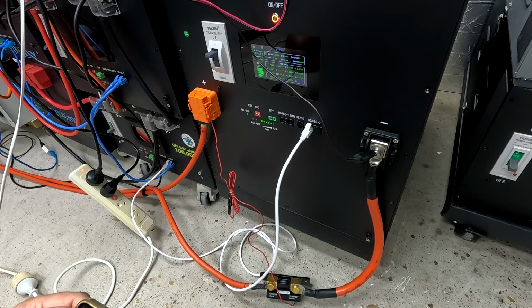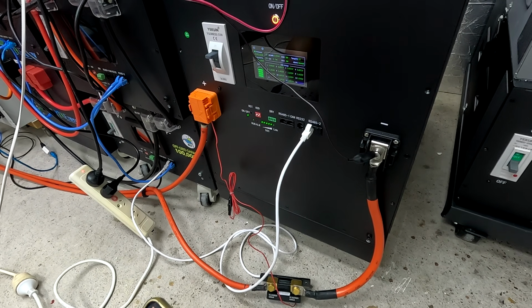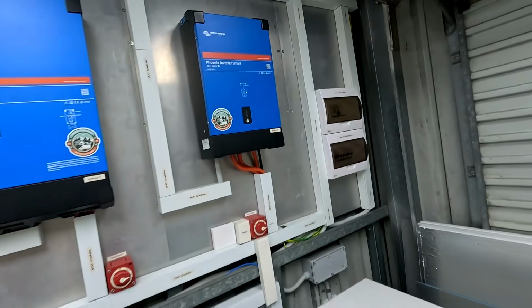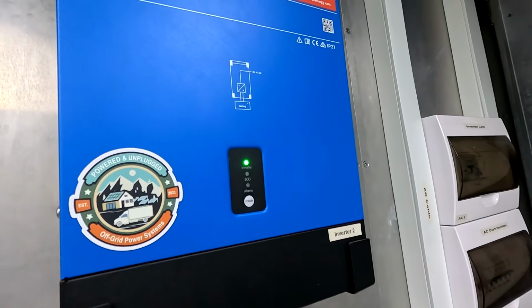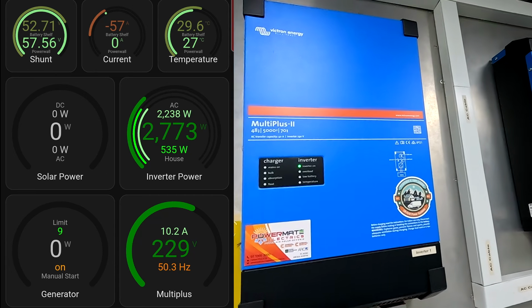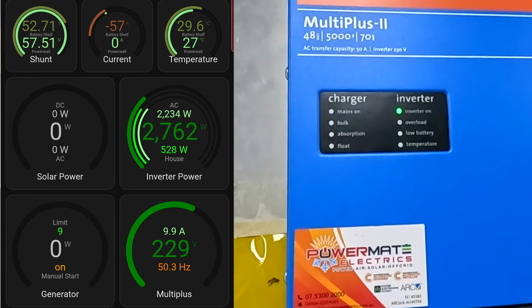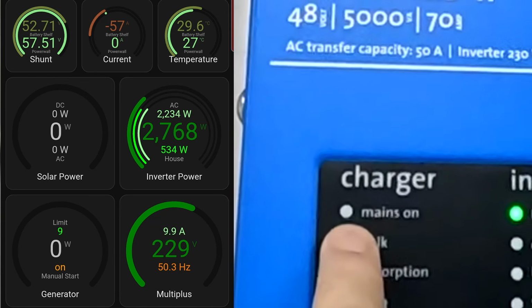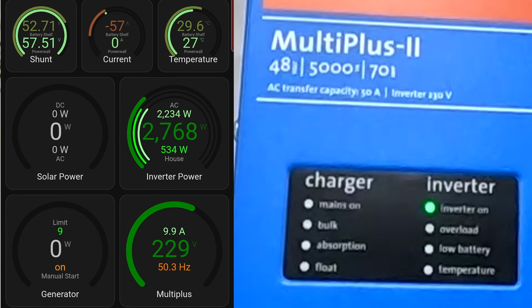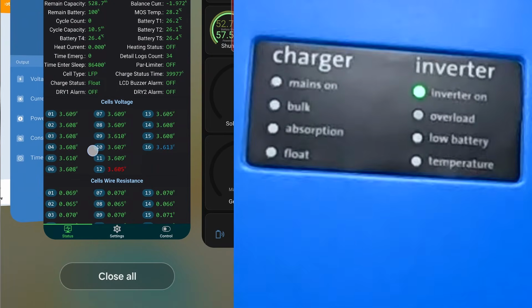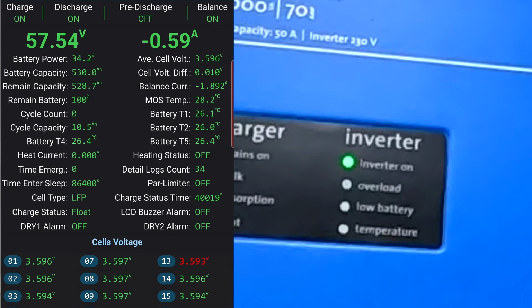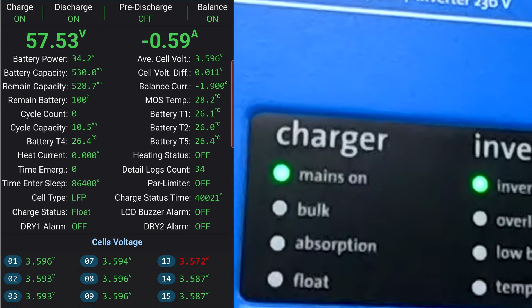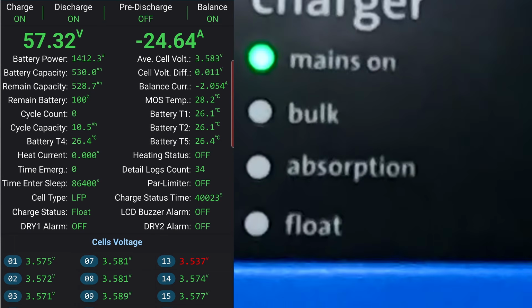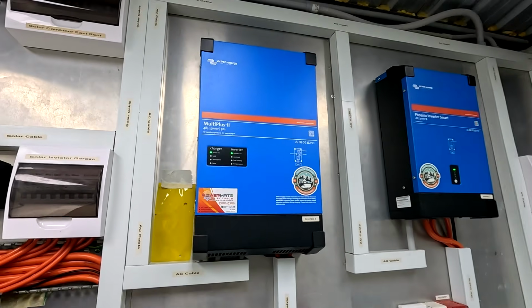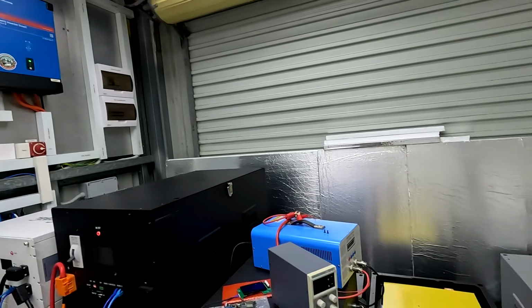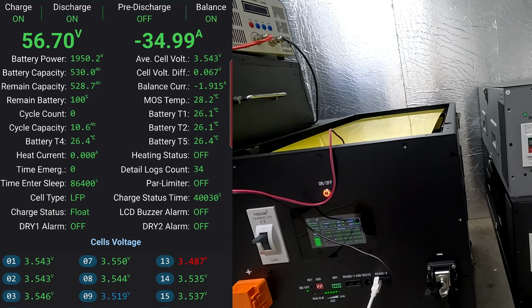I could hear the click of the Sonoff, which turns on the Phoenix inverter, and we should see this one coming on any second. Yes, there's a green light. In another couple of seconds we should see the mains-on light coming on, and then we should see a discharge current here in the JK BMS. It's the standby current - there it is, mains on. And we are discharging our Frankenstein battery, 34 amps only.